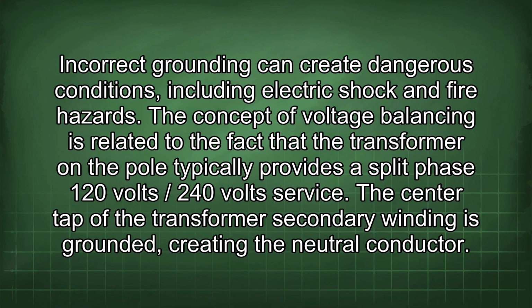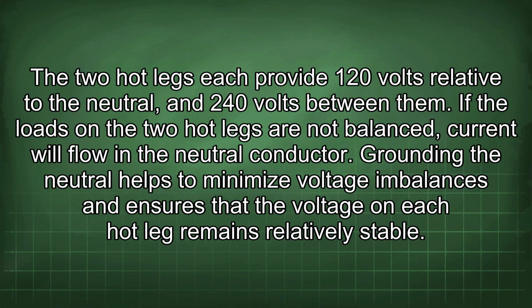The concept of voltage balancing is related to the fact that the transformer on a pole typically provides a split-phase 120 volts/240 volts service. The center tap of the transformer secondary winding is grounded, creating the neutral conductor. The two hot legs each provide 120 volts relative to the neutral, and 240 volts between them. If the loads on the two hot legs are not balanced, current will flow in the neutral conductor. Grounding the neutral helps to minimize voltage imbalances and ensures that the voltage on each hot leg remains relatively stable.